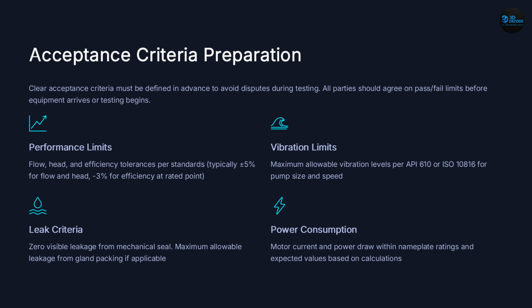Next, acceptance criteria preparation. Now let's discuss one of the most overlooked topics in testing: acceptance criteria. Because if success isn't defined, how do you know whether the test passed? Performance limits must be agreed upon beforehand. Flow, head, efficiency, all clearly defined. Vibration limits must be established, typically using API 610 or ISO criteria. Leakage criteria must be documented, and power consumption expectations must be understood. The worst time to discuss acceptance criteria is during the test, because that's when disagreements become expensive. World-class projects define success before testing begins, not after results arrive.